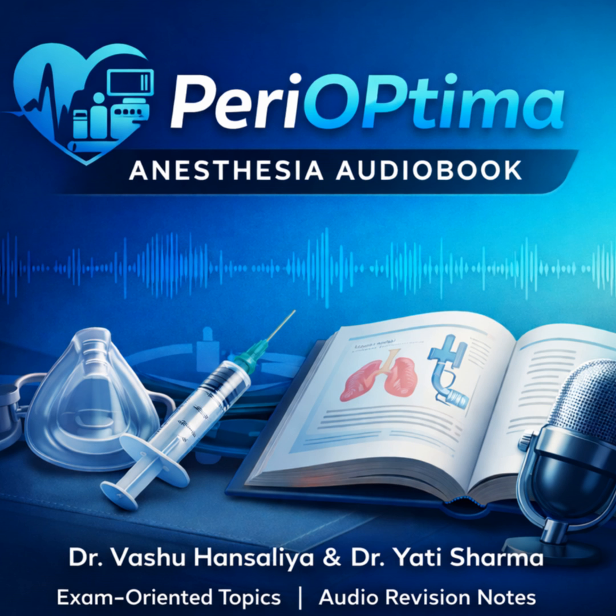But there's also a physics concept called siphonage. Siphonage. Yes. If the pump is placed high above the patient, say on a tall IV pole, without a proper anti-siphon valve, gravity can literally pull the drug out of the syringe, causing a free-flow overdose.